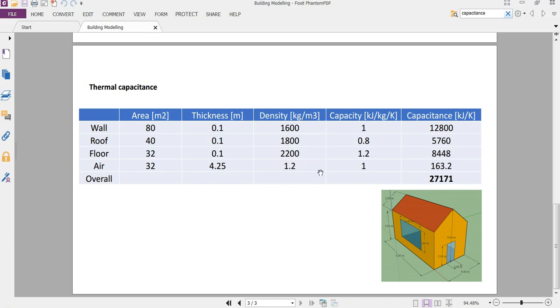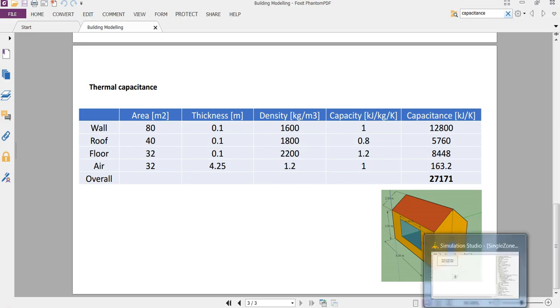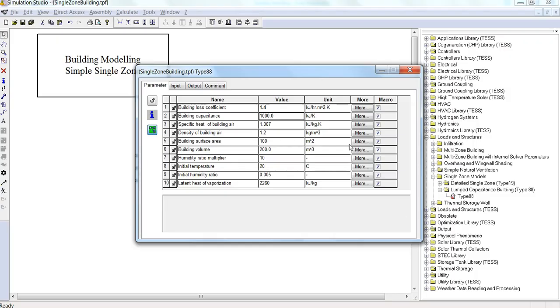The density for each of these, and then the rough amount of thermal capacitance for each. That will give us the total capacitance. By multiplying area by thickness will give us volume, multiply by density will give us mass, multiply by capacity will give us the capacitance in units of kilojoules per kelvin. And that will give us the overall capacitance of the building. So I'm going to put that there, 27,000.